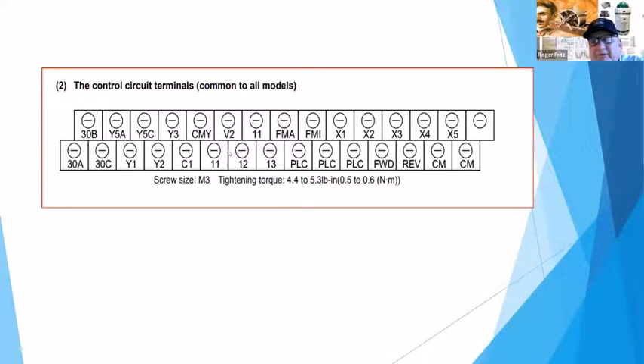So they operate it various ways. Then they have various extra contacts on here. So you can also go and communicate to other PLCs. And that's why this is here. Or you can communicate to other processors and sequencers. So that's when it comes into whether you've got Modbus, CANopen. Most of those are very similar, what they call protocols, which are just sequences of telling the communications between the two processors.